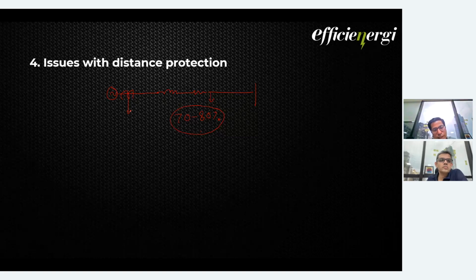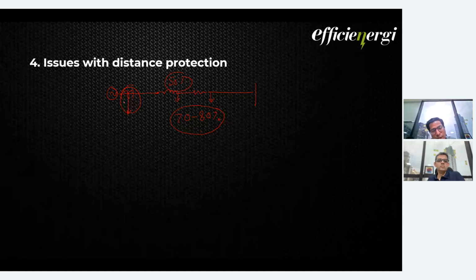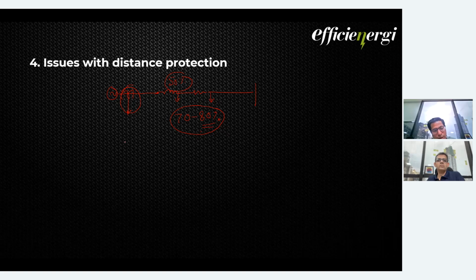So what will happen if there is saturation in this CT, instead of 80% of the line protection or 80% of the fault coverage, it may see a fault at a reduced level, possibly 50%. At what time the CT gets saturated tells you what maloperation it will have. If there is no saturation, all 80% is covered. But suppose, maybe at 7 milliseconds, it gets saturated, then it will be in the range of 15 to 20%. So even in distance protection, saturation becomes a very big problem.